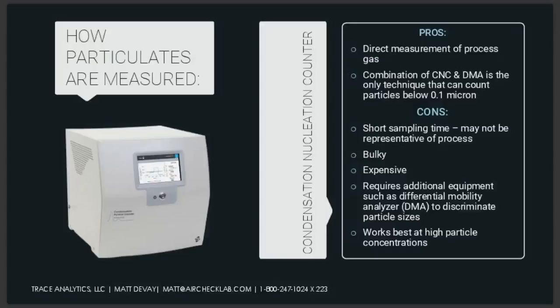The cool thing about these is that if you have the need to see particles below 0.1 micron, this is the only way that you can do it. And then all those same caveats as far as why you wouldn't use it apply. They're heavy, they're expensive. These also have consumables, so you need some kind of liquid to vaporize. They require calibration. And one other caveat about this guy is that it works best at higher particle concentrations. So if you're trying to achieve lower classes, they lose accuracy at lower concentrations.